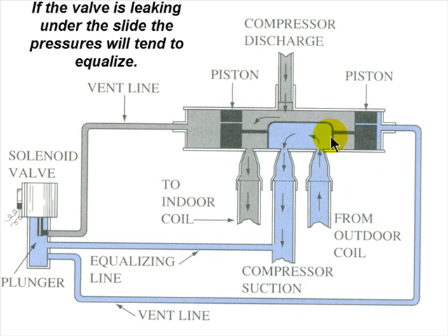Anyway, if the valve is leaking under this slide, if there does develop a gap in here somehow, then the pressures will tend to equalize. Because look what you got here. Here's your slide. That's one pressure. The other pressure, the higher pressure, is on the outside of it. So if there's a leak in here anywhere, the high and low are going to equalize or tend to equalize. Your low pressure is going to get high. Your high pressure is going to get low. That's a typical symptom of a leaky slide inside of a reversing valve.